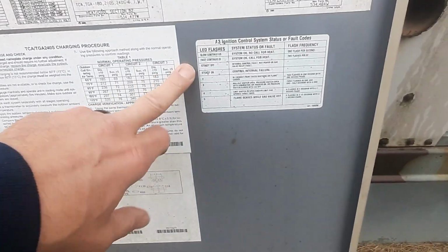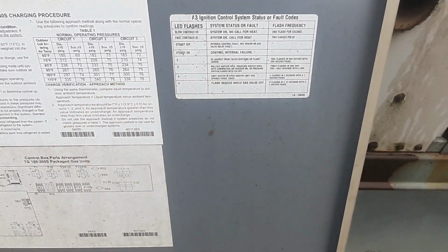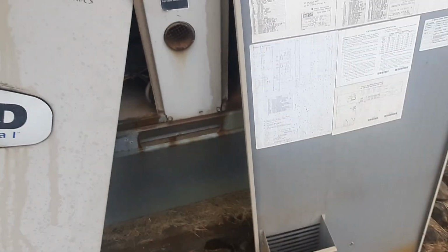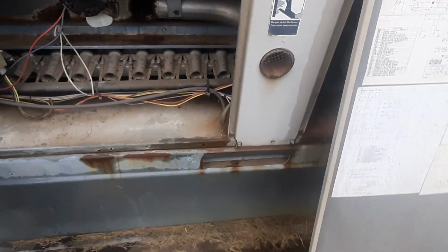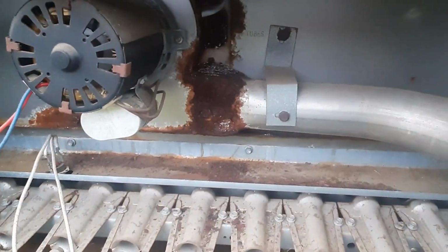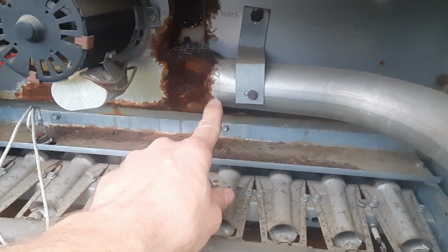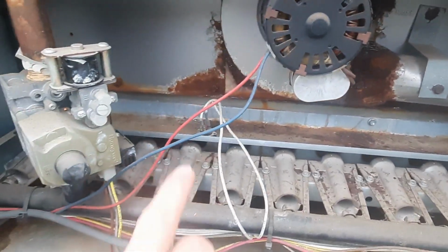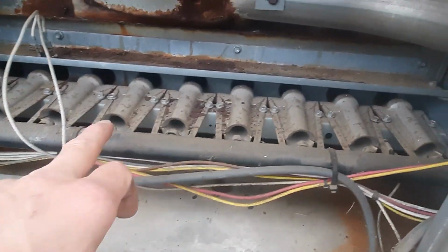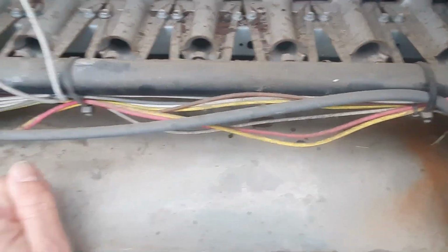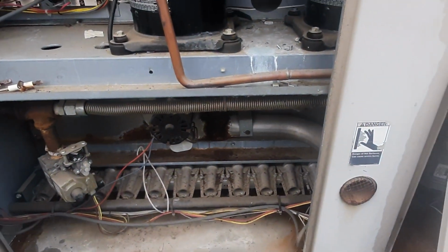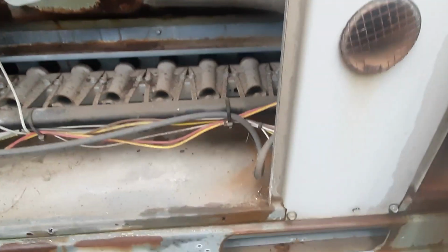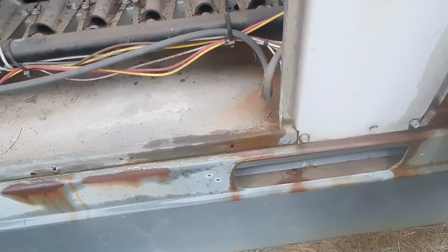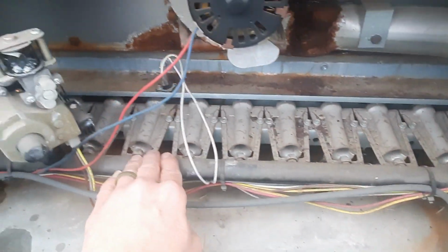So I found my flash codes. It's 4, limit switch open, or has opened 3 times. So we got a limit switch open. The heat exchanger is liable to be cracked because this looks bad. That whole plate's rusted, and everything needs to be cleaned. You can see all the dust and crap in the burners. All this needs to be cleaned out real well. But let's start with the blower then. That rollout switch is loose too.